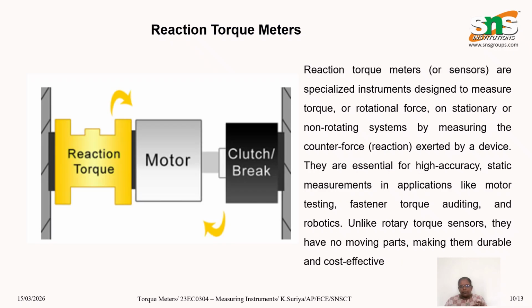Another important type is the reaction torque meter. Unlike rotary torque meters, reaction torque meters are used for stationary or non-rotating systems. They measure the reaction force generated when torque is applied to a component. Since they do not contain moving parts, they are highly durable, reliable, and cost effective. Reaction torque meters are widely used in motor testing, calibration laboratories, robotics, and fastener torque verification systems.